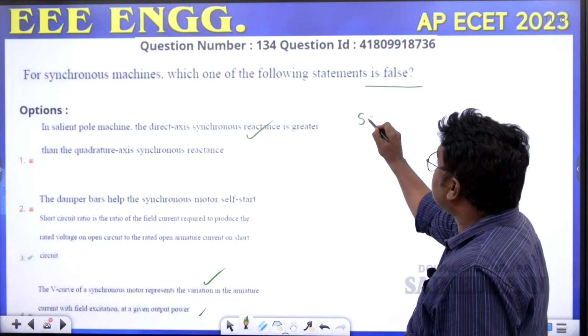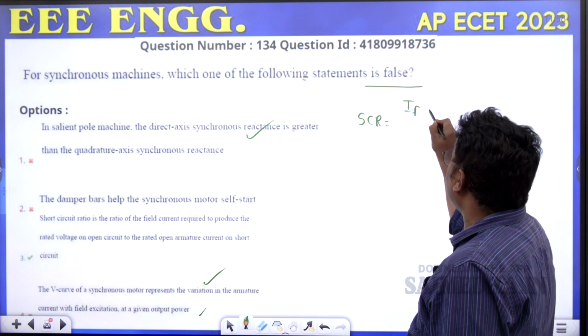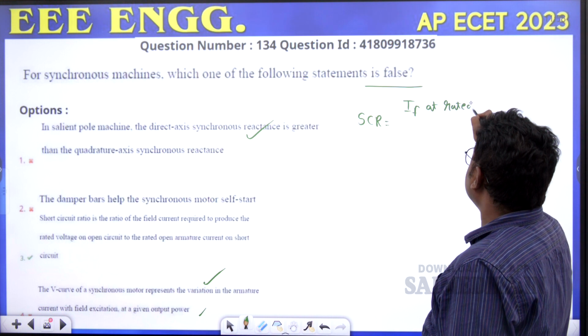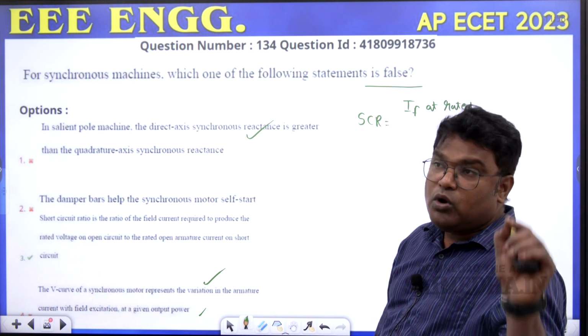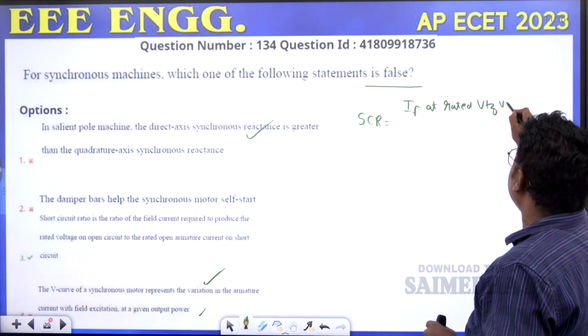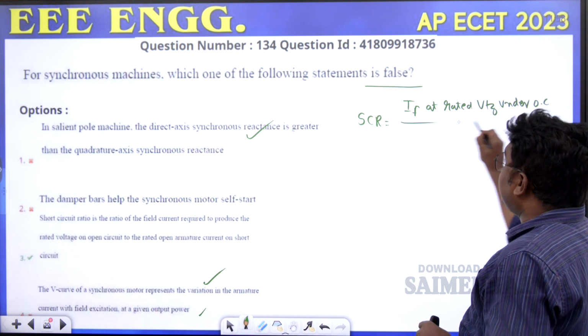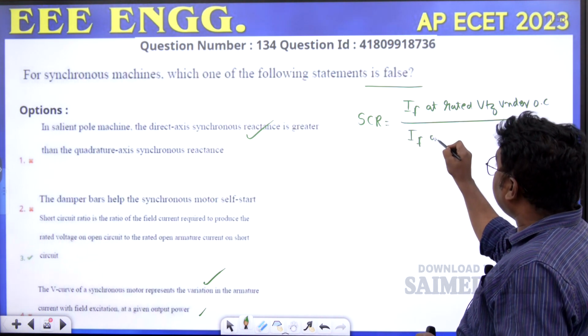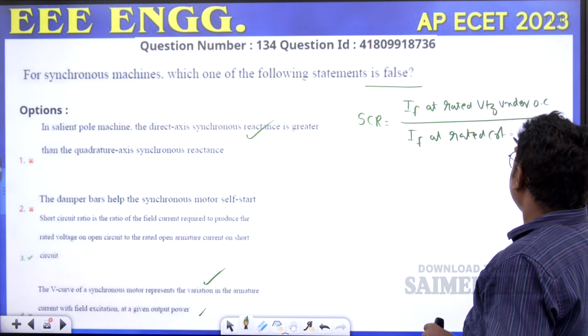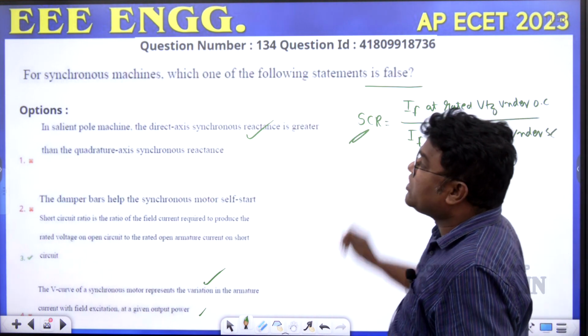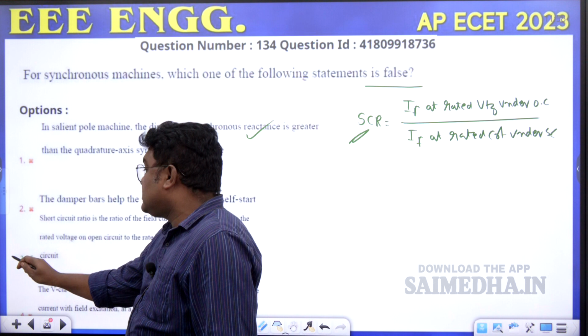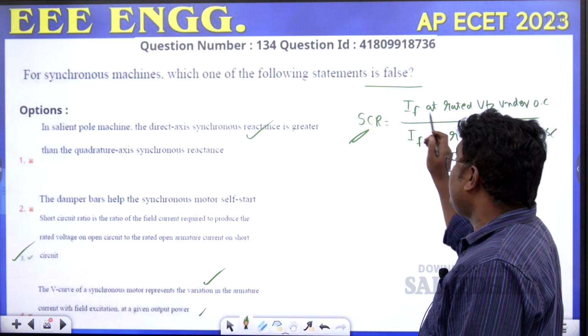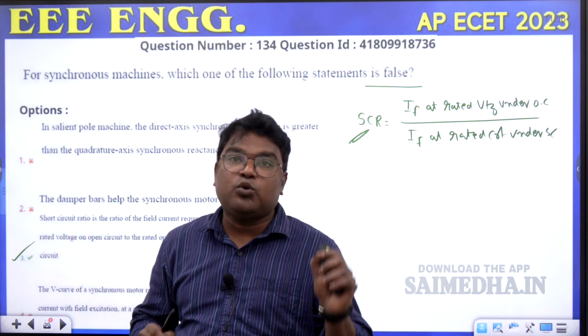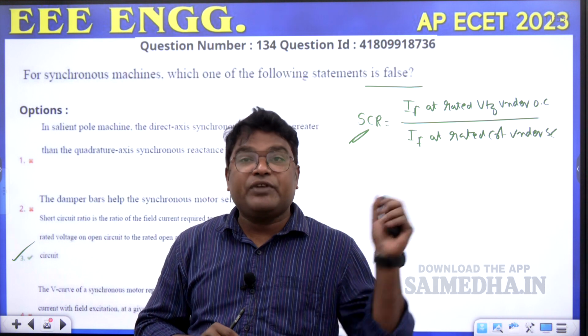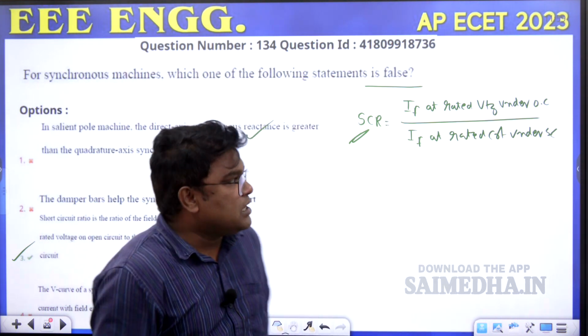Now actually SCR, the short circuit ratio, is the field current required to produce the rated voltage under the open circuit condition, divided by the field current at rated current under the short circuit condition. This is the short circuit ratio. So the answer for this question, option 3, is the wrong statement. Actually it is the ratio of the field current required to produce the rated voltage under open circuit to the field current required to produce the rated current under short circuit condition. That is the SCR, short circuit ratio.